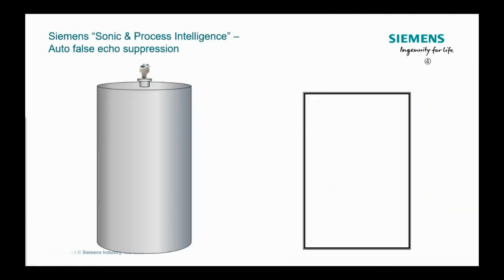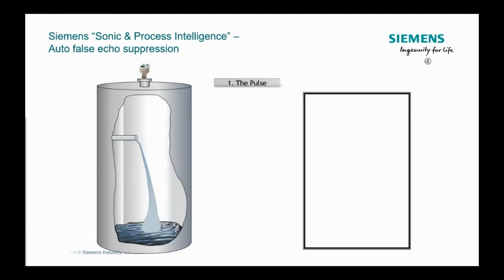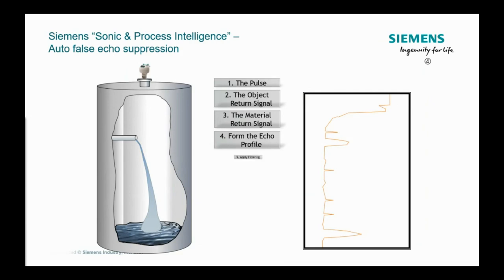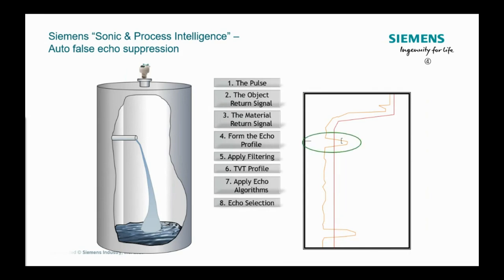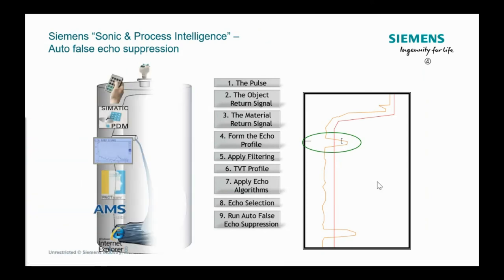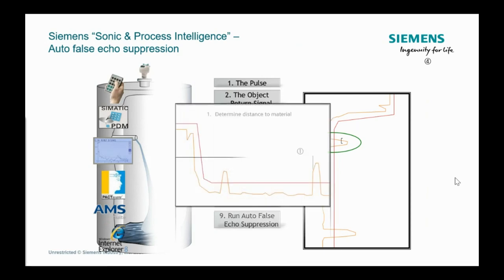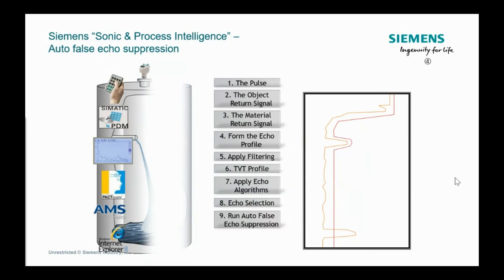Okay, so if we go to the "how do you do it" slide, here's the official slide of how to do it. We've got a pipe sticking out there. We've got a return off both the pipe and the material. We apply some filtering. We do a TVT. I've got two valid echoes. We apply echo algorithms, and voila, it selected the wrong echo. So then you go through and run auto false echo suppression. You can do it with the handheld, SIMATIC PDM. Some of the units you can do it from the push buttons. PACTware and AMS Suite have the ability to do that. You can use Internet Explorer with the LUT400 series. So you can do it a couple of different ways. But you apply auto false echo suppression. You basically figure out what distance you want to learn to, perform a learn function, apply it, and voila, you have one valid echo left.